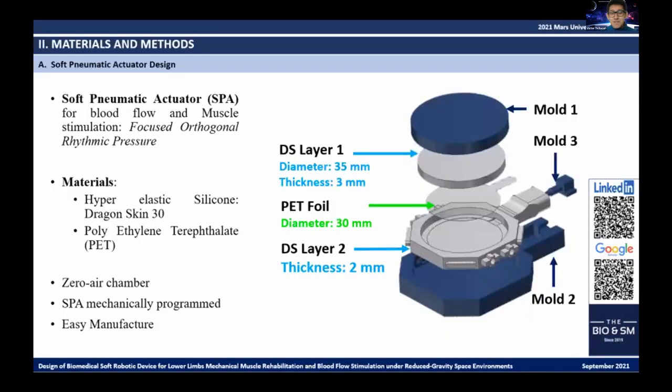The design of these soft pneumatic actuators (SPAs) provides the capacity to stimulate muscles during hypogravity exposure to avoid atrophy and promote blood flow in the lower limbs. For fabrication, we use the hyperelastic silicone Dragon Skin 30 because of its higher Young's modulus than other silicone materials and for being ideal for vibrating applications. Additionally, we used polyethylene terephthalate (PET) to form the zero-air chamber and prioritize one-direction deformation, since PET is both non-extensible and flexible. With these materials and design features, the SPA is mechanically programmed to concentrate deformation energy towards one direction, and the manufacturing process is significantly simplified.